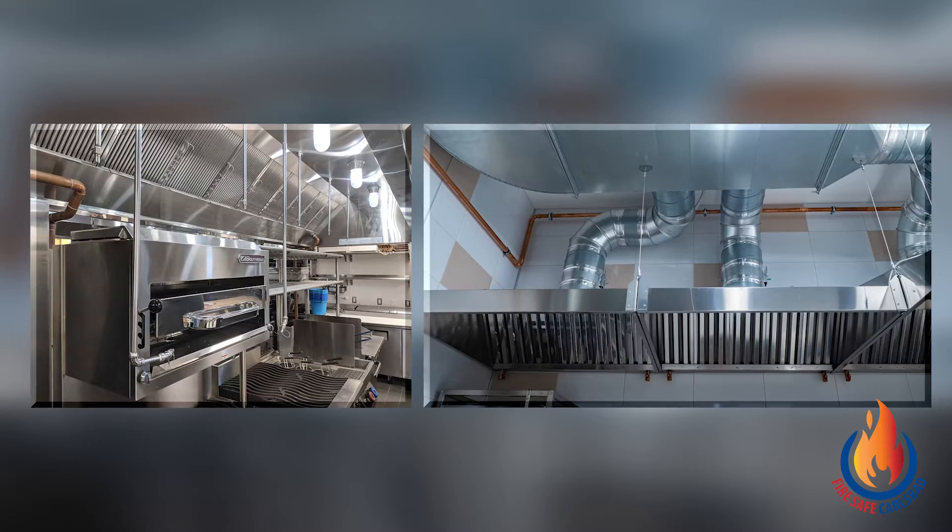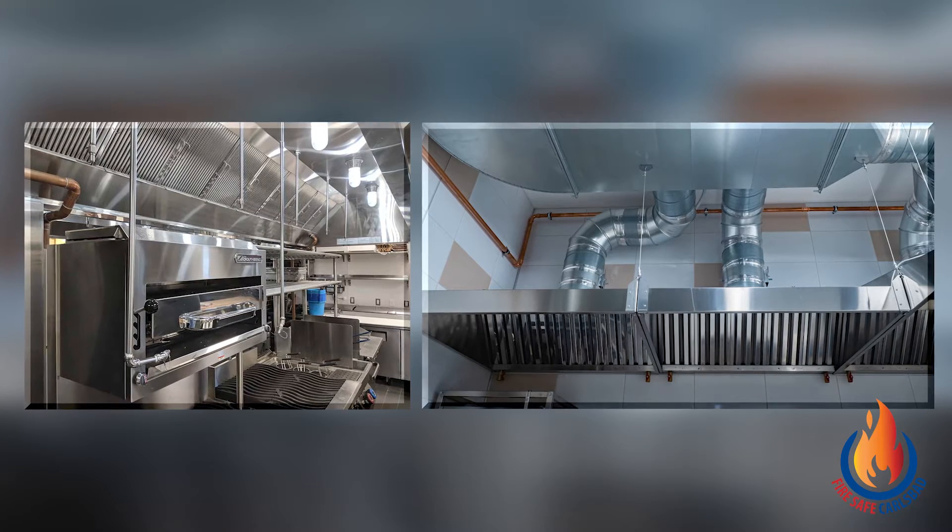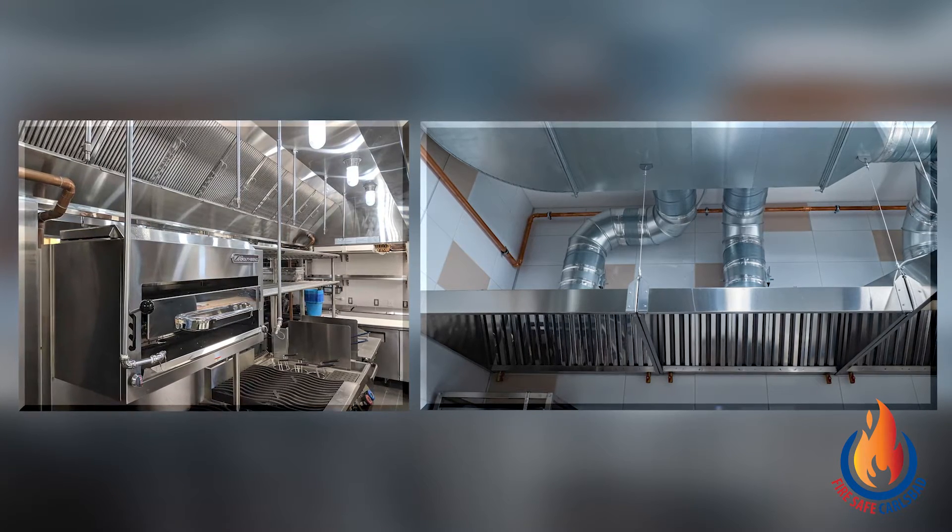Hi, I'm Edie Maldonado. Your kitchen's hood and fire suppression system is designed to provide fire protection for your cooking appliances, plenum, and ducts. Your hood and exhaust system is designed to remove grease-laden vapors from the kitchen. The suppression system is designed to extinguish fires underneath your hood. Although these systems are separate, they do work together. This video will cover how these systems work, how they are maintained, and the service intervals that are required for them.